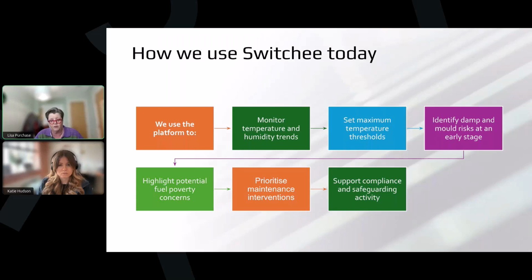But what we found was that our tenants weren't warm enough in cold snaps, so we increased that maximum temperature to 23 degrees, and actually people are very comfortable within that temperature, and we don't find any kind of overheating issues at all now. We've got that maximum temperature, and we haven't received any complaints since we've increased it.